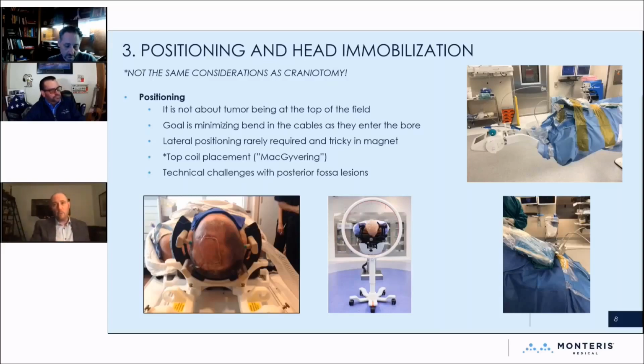In fact, the most important thing for positioning in these cases is that the cables are going to come out of the head at an angle. If you look at the bottom right picture here, you can see that the cables are coming at maybe a 35-degree angle or so. I don't know. But the point is, if they're coming straight up out of the patient's head, they have to make a 90-degree turn into the bore of the magnet when you roll the magnet over the patient.